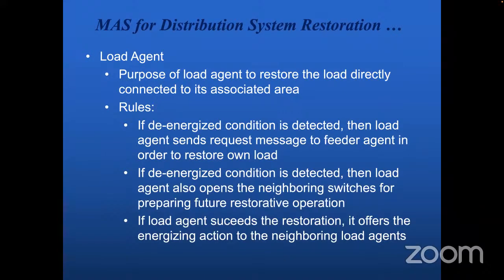Rules: if a de-energized condition is detected, how do you detect it? Simply by seeing the voltage, or maybe current, but current is not the right way, because if you turn off all your loads, you will see current is zero. So a better way is to look at the voltage.